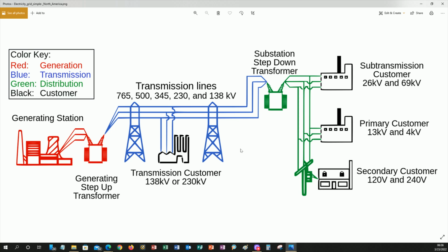That line overloading trips out, causing a voltage collapse. Everything eventually goes to voltage collapse when you have a big blackout. Individual lines can be overloaded, but the blackout where you lose an entire state or an entire region of the country, that's a massive voltage collapse on the transmission grid that cascades and knocks everything else out.